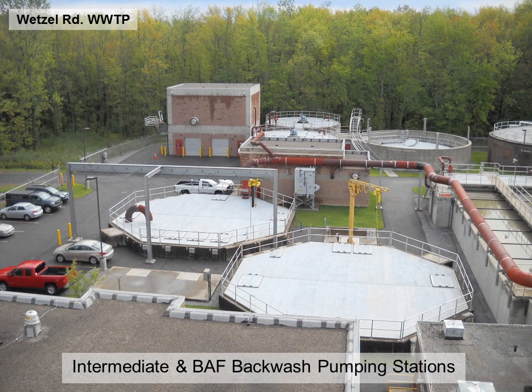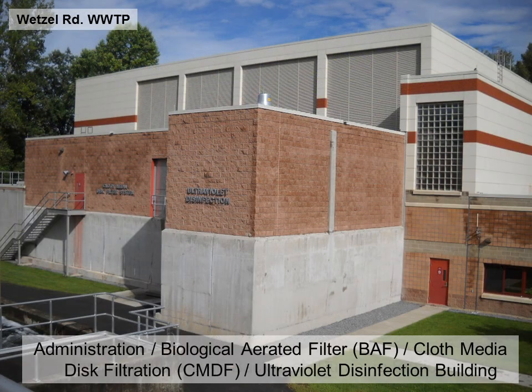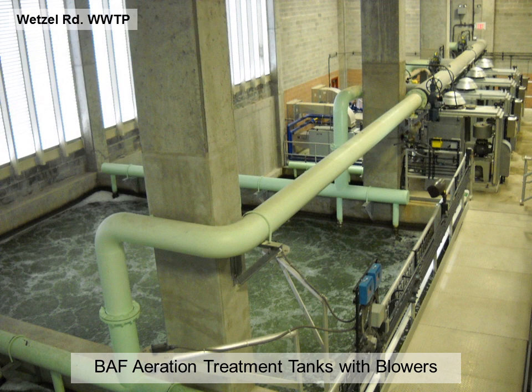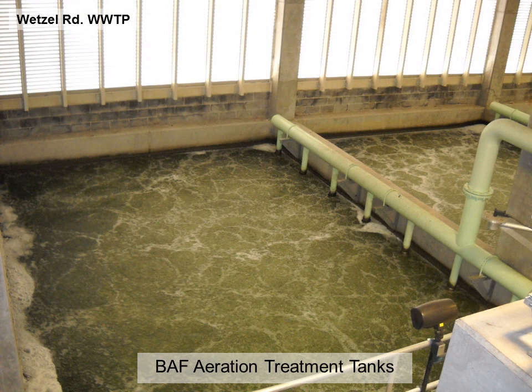The primary effluent is collected and is pumped up to the BAF where it will undergo biological treatment. Advanced treatment of the wastewater occurs in the biological aerated filter tanks, otherwise known as BAF. Wastewater passes through a sand media where biological nutrient removal occurs. Air is added to these tanks to encourage biological activity.